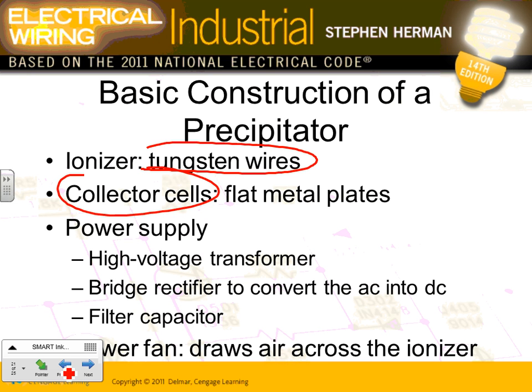Collector, these are your filters, collect all the junk stuff, and you have to have a power supply, which provides you with a high voltage transformer with a bridge rectifier and some filter capacitor. So you take AC, filter it to DC, dump it across a wire, throw the air through it, charge your air positive, and the filter is negatively charged. All these particles that are charged positive are going to stick to the negatively charged filter. And that's how you clean the air.